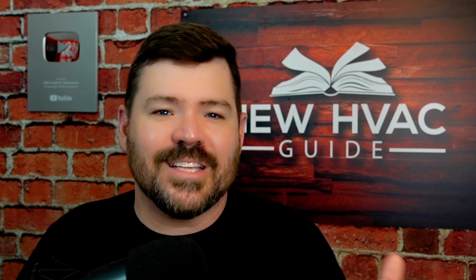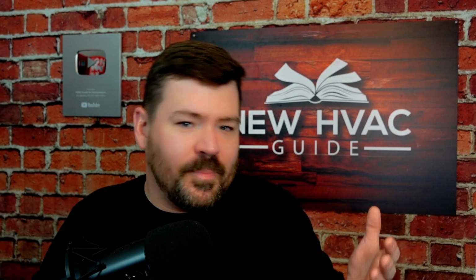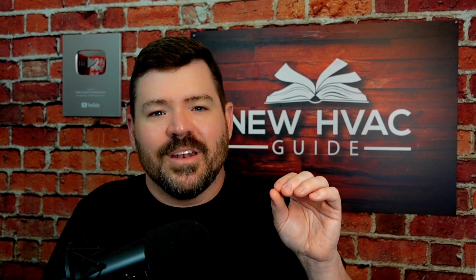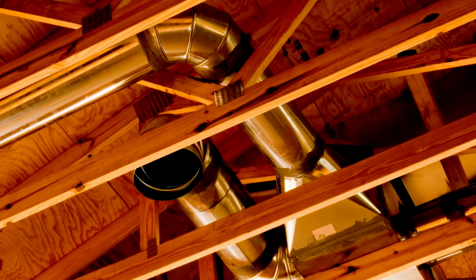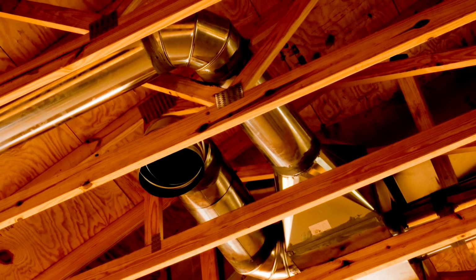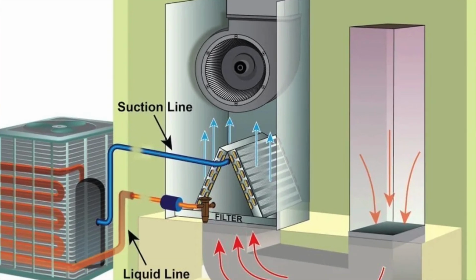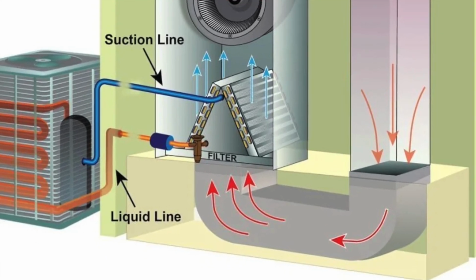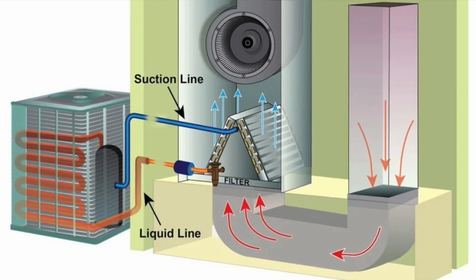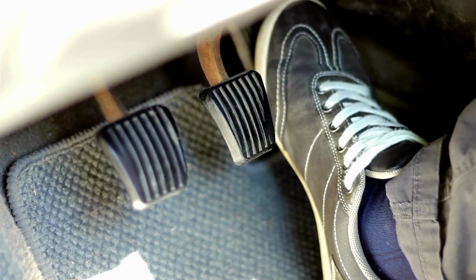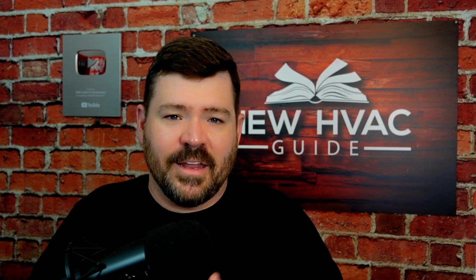I wish it was. I wish that system could magically know that it's installed with undersized ductwork and say, oh, I have the capability of being a 5-ton system, but I'm in a space that's only needing 2 tons of capacity, and the ductwork is probably undersized, so only 1.5 tons of capacity. And so I'm just going to ramp down. I know I have this capability of being this jet engine, this big diesel motor, but because I can let my foot off the gas and ramp down, it's just going to magically work that way. And that's just not how it works.